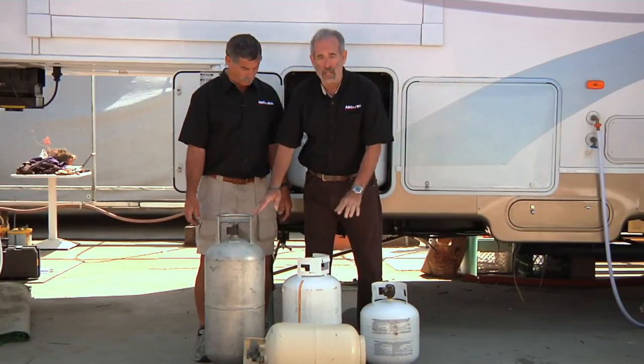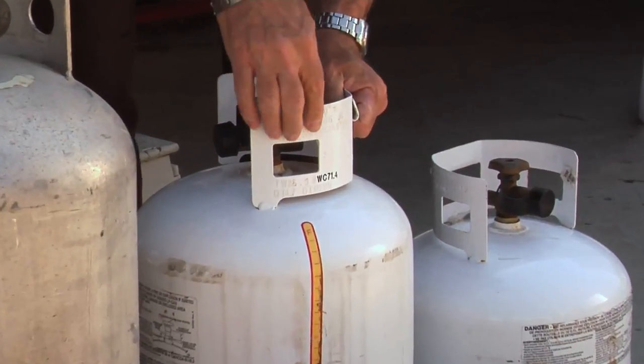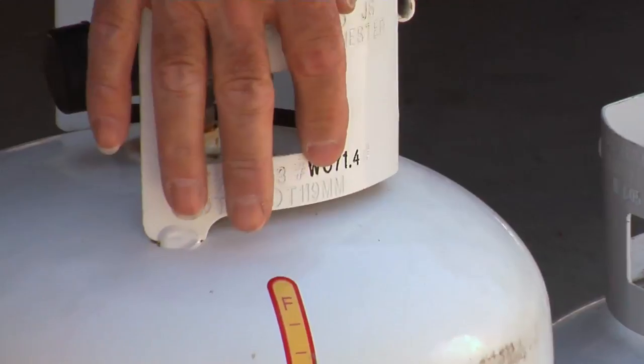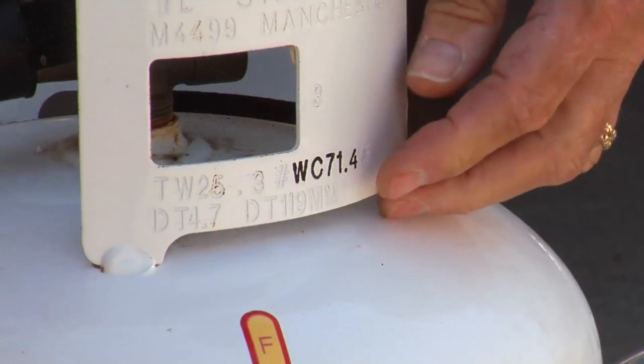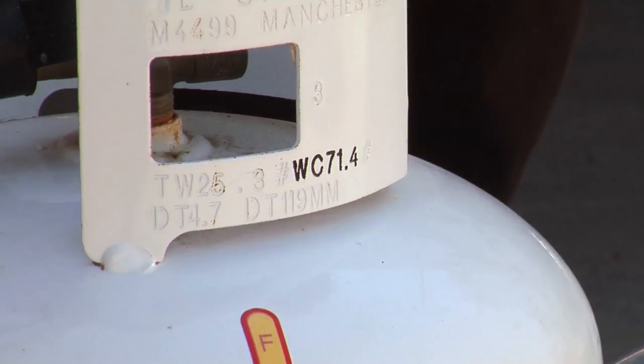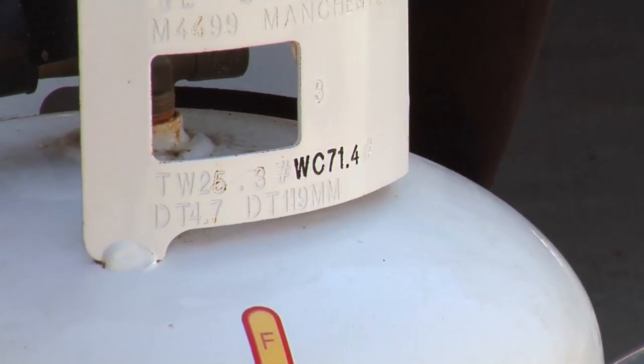Every one of these cylinders has a guard that protects the valving. On the guard, you'll see a stamped number that says WC — that's water capacity. The number right next to that, in the case of this cylinder, is 71.4. If you take that decimal point and move it one place over, that gives you 7.1 — a seven-gallon propane cylinder.